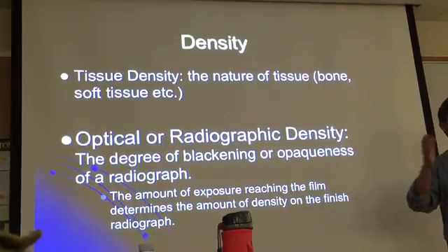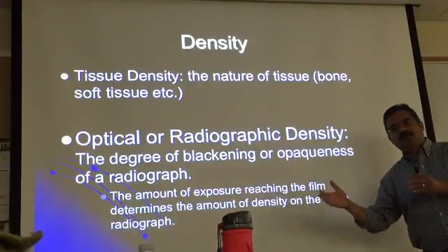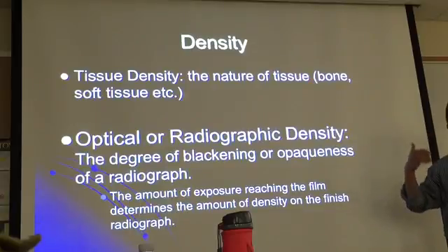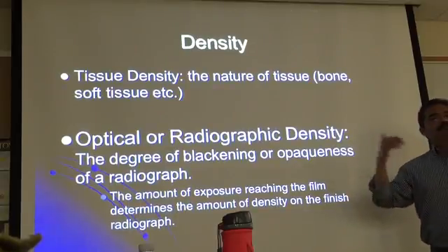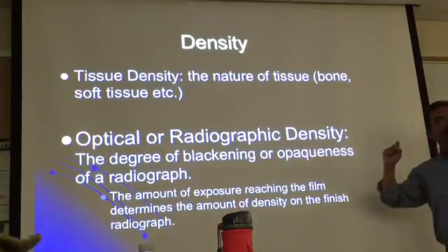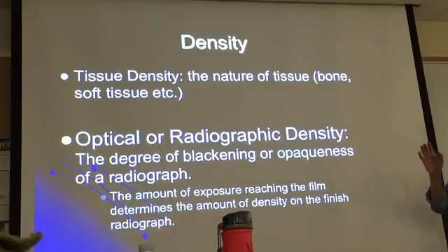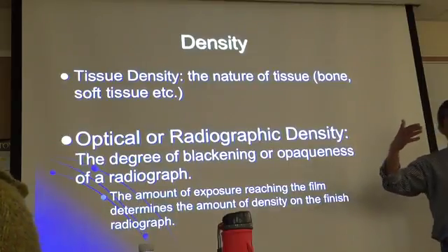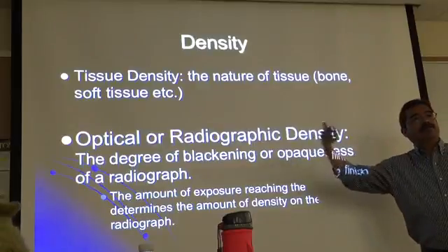You can change if you want it darker or lighter. You have more influence after the image has been done. Do you guys remember when we first looked at CR systems, I told you there is a mode called the fixed mode? The fixed mode acts just like film. If we were to use our system in fixed mode, then whatever exposure will represent that specific density.